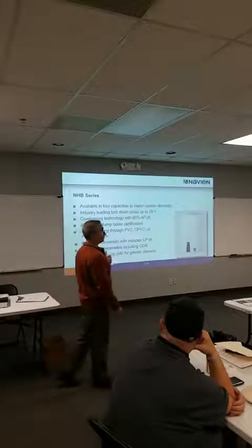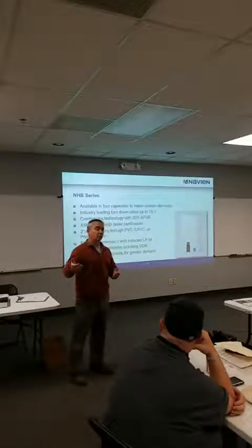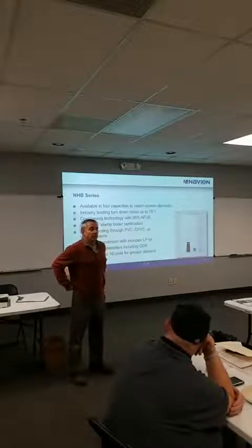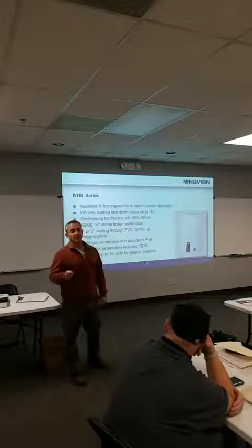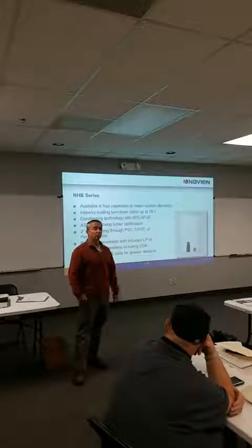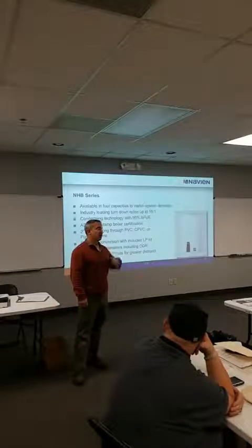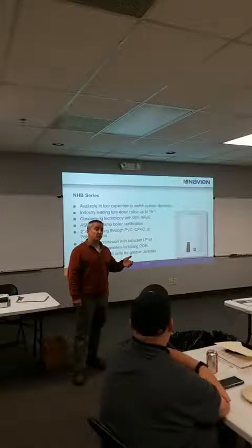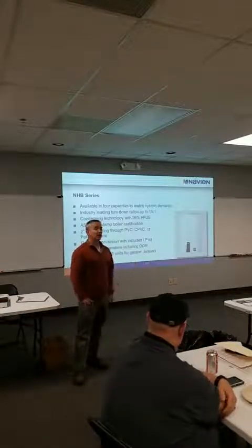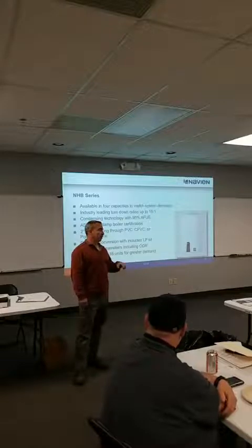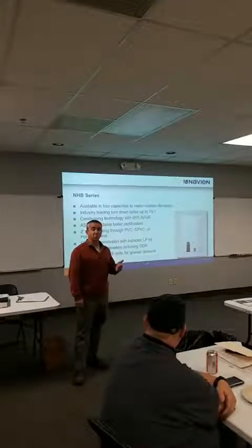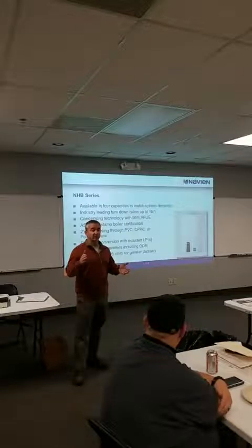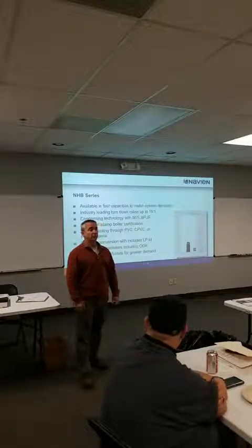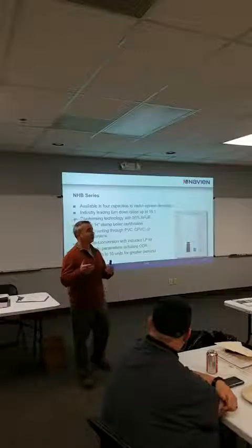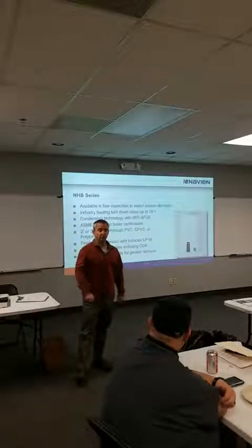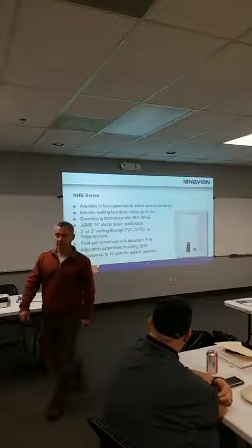So these units, if you're doing outdoor reset, they will get up to like 194. Without outdoor reset on the keypad, really 180 is what you can go to supply temperature. But that is going to increase to 185 as well. With outdoor reset, it actually will run to 194. And they all have a programmable 30-minute boost at 30%. So we can even go higher than that if we're not maintaining temperature. You can program boost into those for up to 30 minutes, and that'll jump you another 30%.